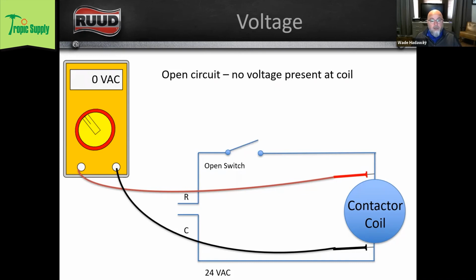If we open the switch, interrupt the circuit, right? We have interrupted the flow of electrons. So we check our voltage at our coil, and it's not there because our electrical potential is now sitting right here at the end of this switch, waiting for this switch to close. As soon as the switch closes, the electrons are going to continue to flow, and we'll have 24 volts at our coil.